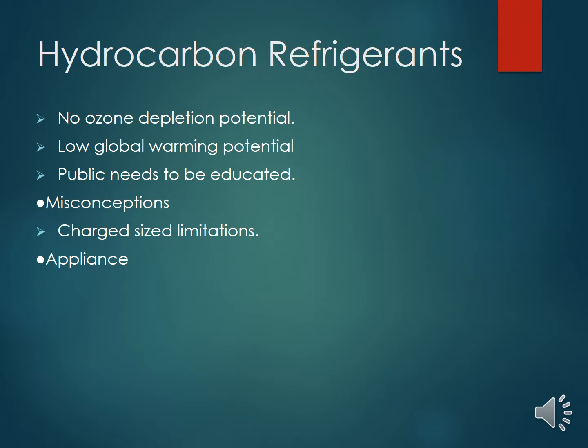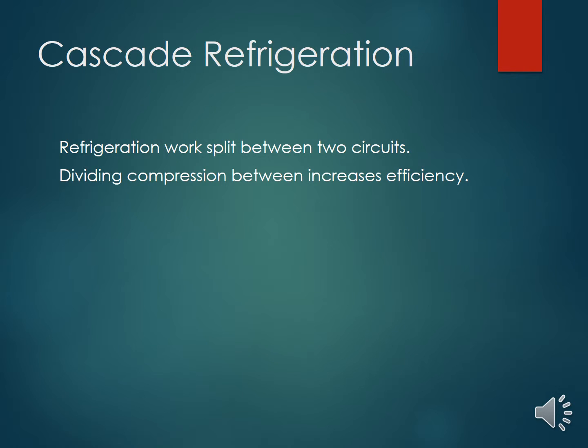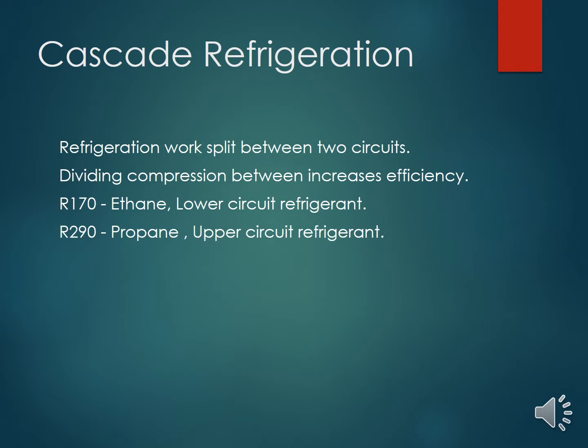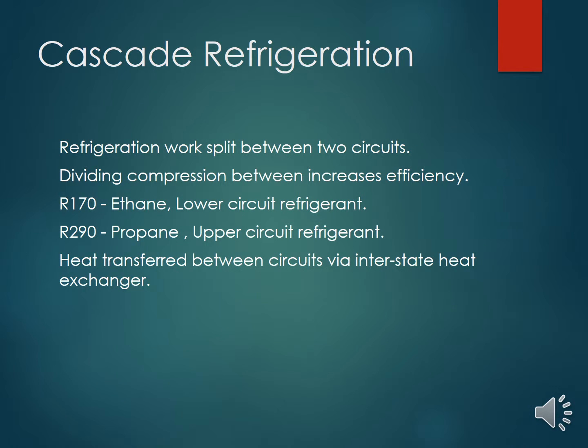The primary use would be in appliances. Typically 4 ounces is the size of the charge that is currently used. In large commercial plants, the plants are located away from areas where they can pose a threat to the public. In the cascade refrigeration system, the heat is removed from the refrigerated space and rejected to the atmosphere in 2 stages. This is more efficient than a single stage compression system. Heat is rejected from the R170 to the R290 via an interstage heat exchanger.